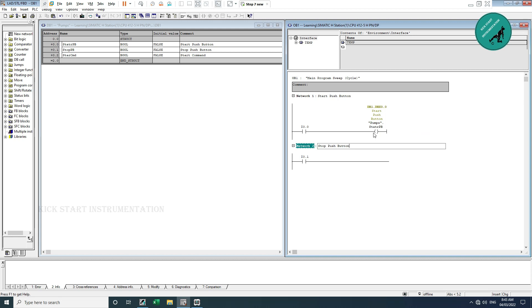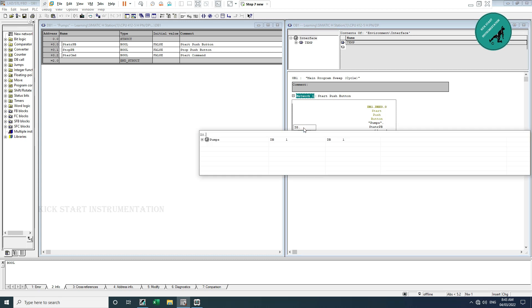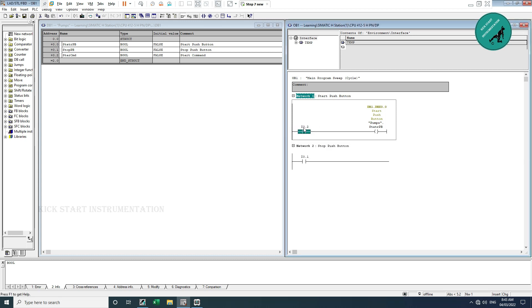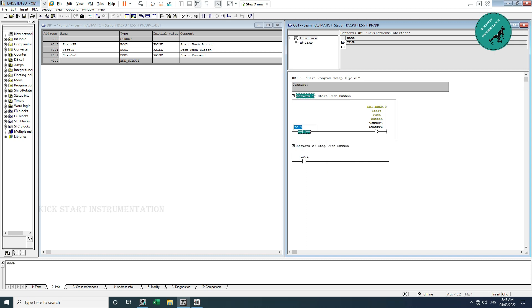To avoid this during diagnostics, I am mirroring I0.0 to this signal. So wherever I previously would have used I0.0, I am instead going to use the 'start pushbutton' signal. That way, if I want to change the address, I only need to change it here — and that change from I0.0 to I0.2 will be reflected everywhere automatically.